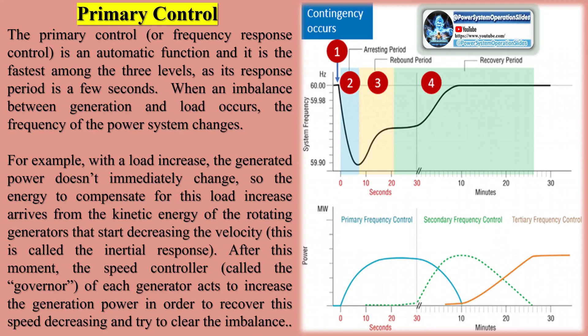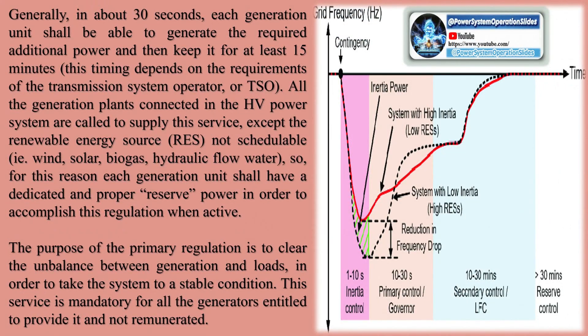Frequency variations in a power system occur because of an imbalance between generation and load. When the frequency value of a power system reaches the emergency condition, the control strategy is initiated. The frequency control is divided in three levels: primary, secondary, and tertiary controls. Each frequency control has specific features and purposes. Primary control, or frequency response control, is an automatic function and it is the fastest among the three levels, as its response period is a few seconds.